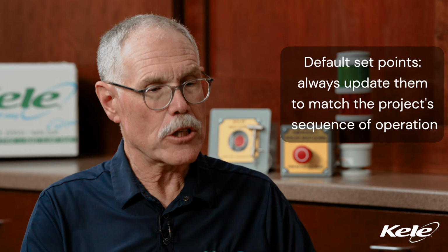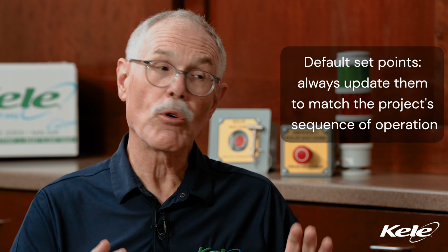So during the commissioning process, there are always set points that somebody has determined as a good base starting point. Do those always stick, or do they need to be changed later? That's a great question. The answer is you always want to make sure you go through and check that the default set points that came in the software or the program match what the sequence of operation for this project is calling for. And this is the famous 72 degrees, parentheses, ADJ, adjustable.